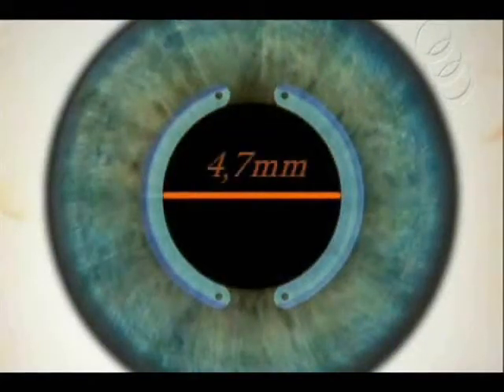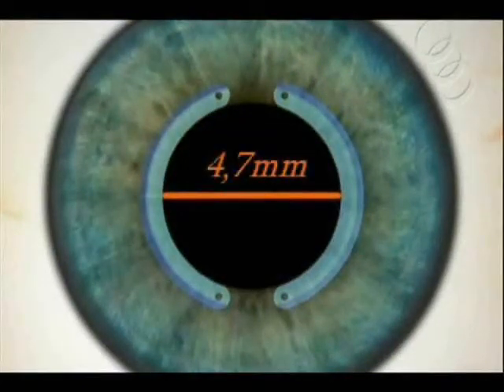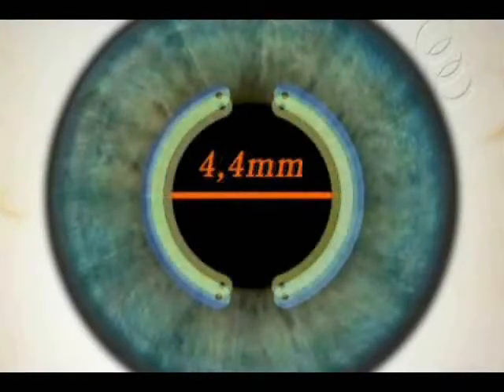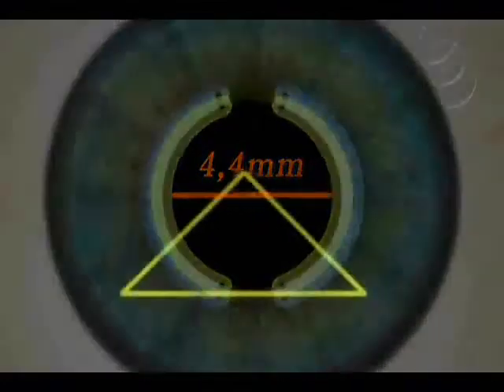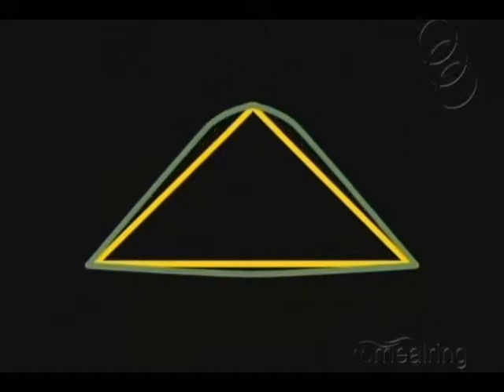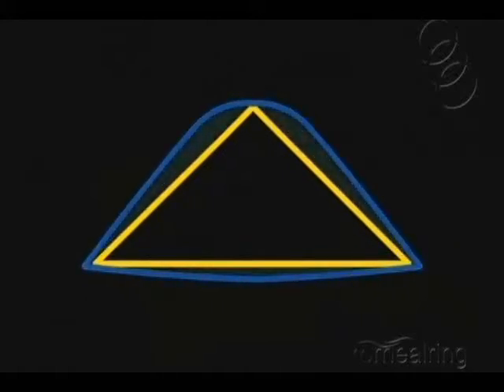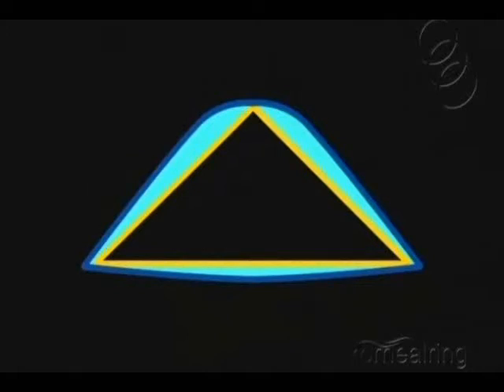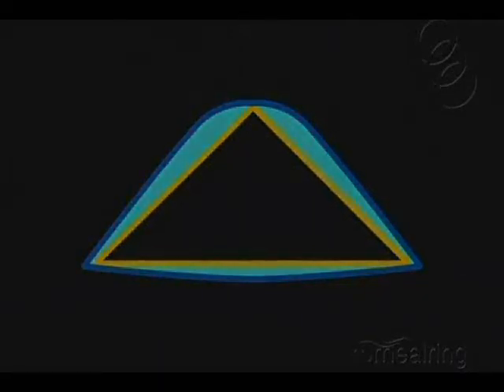The corneal ring internal diameter was increased to 4.7mm as compared to the smaller 4.4mm from the old triangular model. This improvement was obtained without losing the ability of reducing the corneal curvature, thanks to its innovatory mass-addition design, which makes it more efficient, keeping the same flattening power of the old triangular cross-section segment with the same thickness.